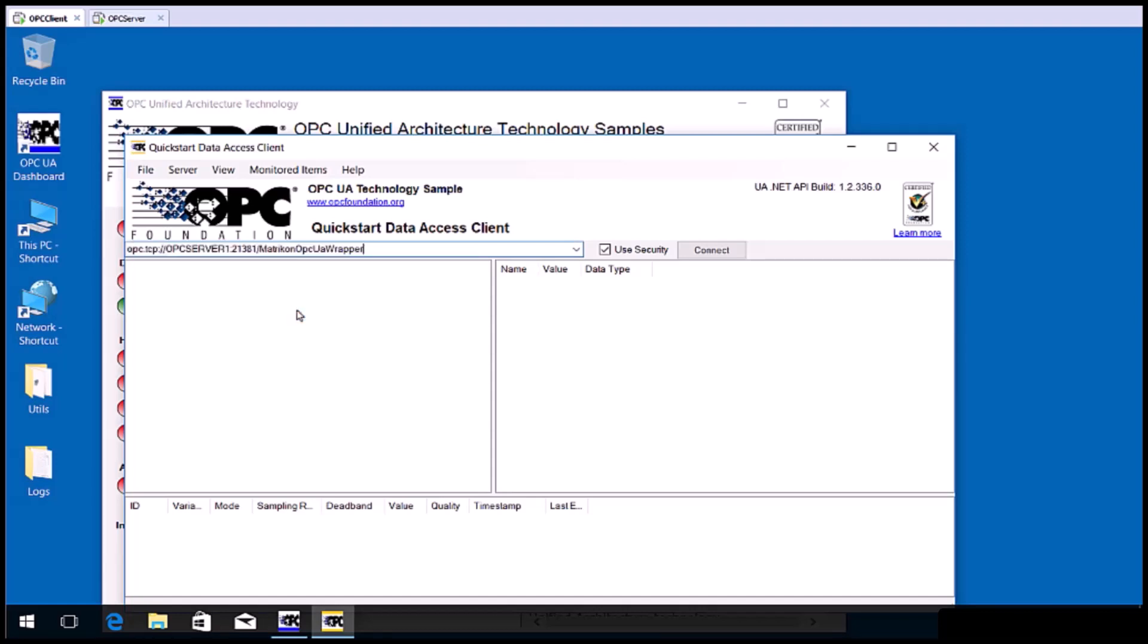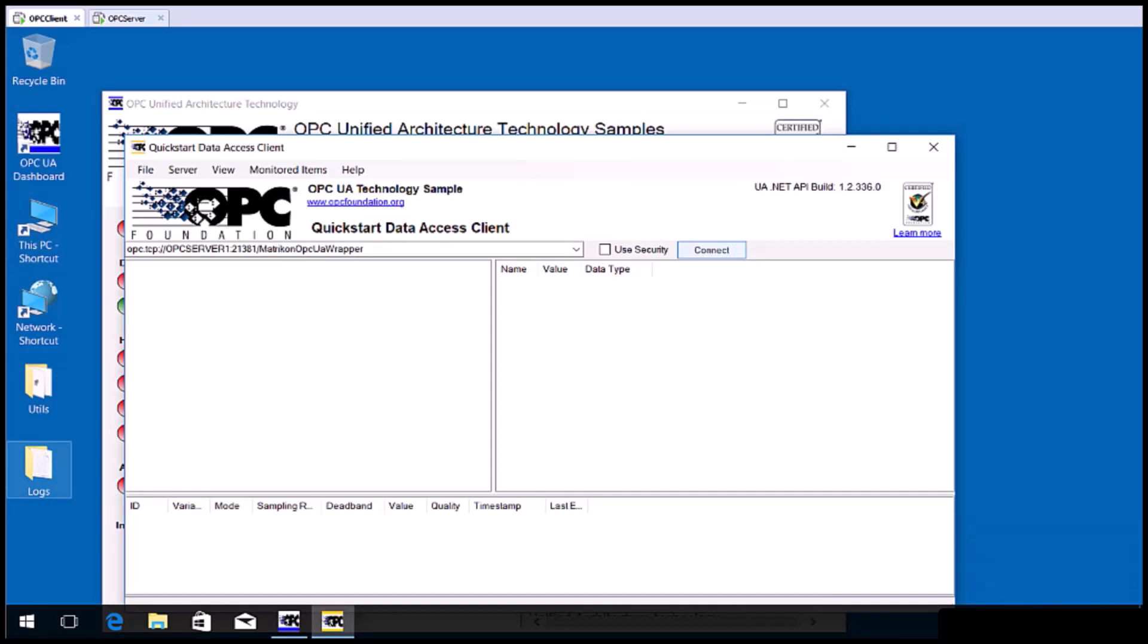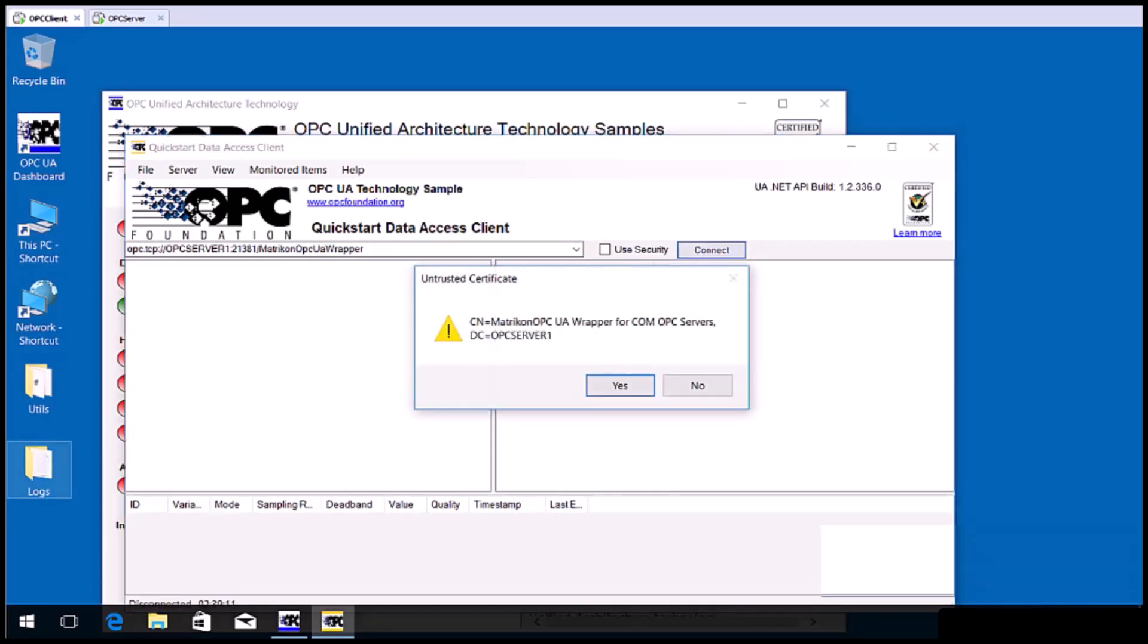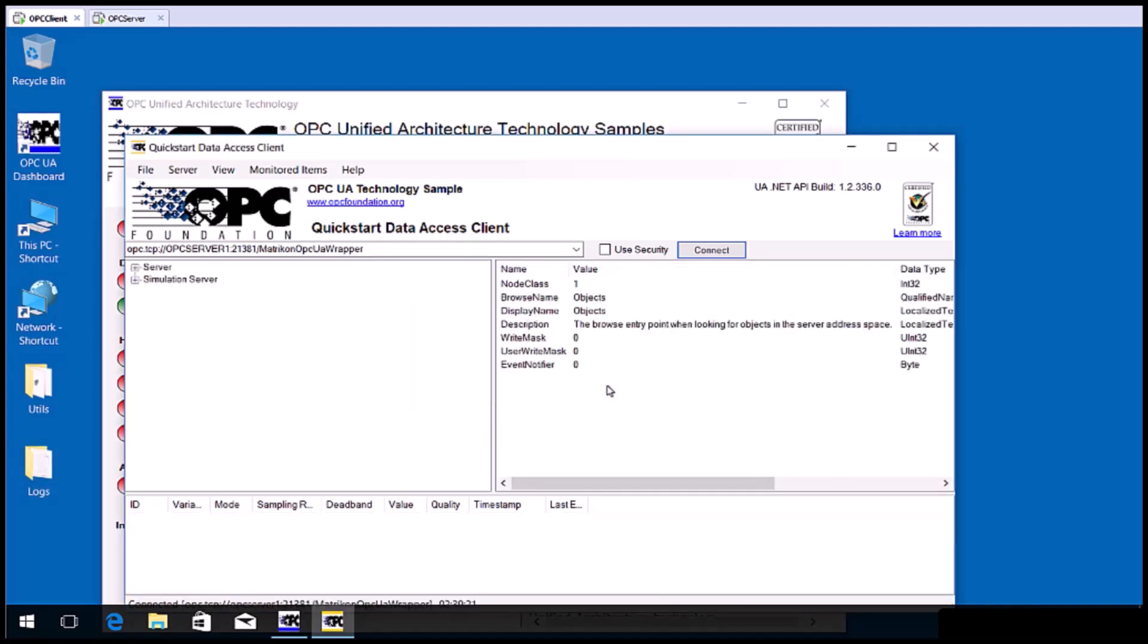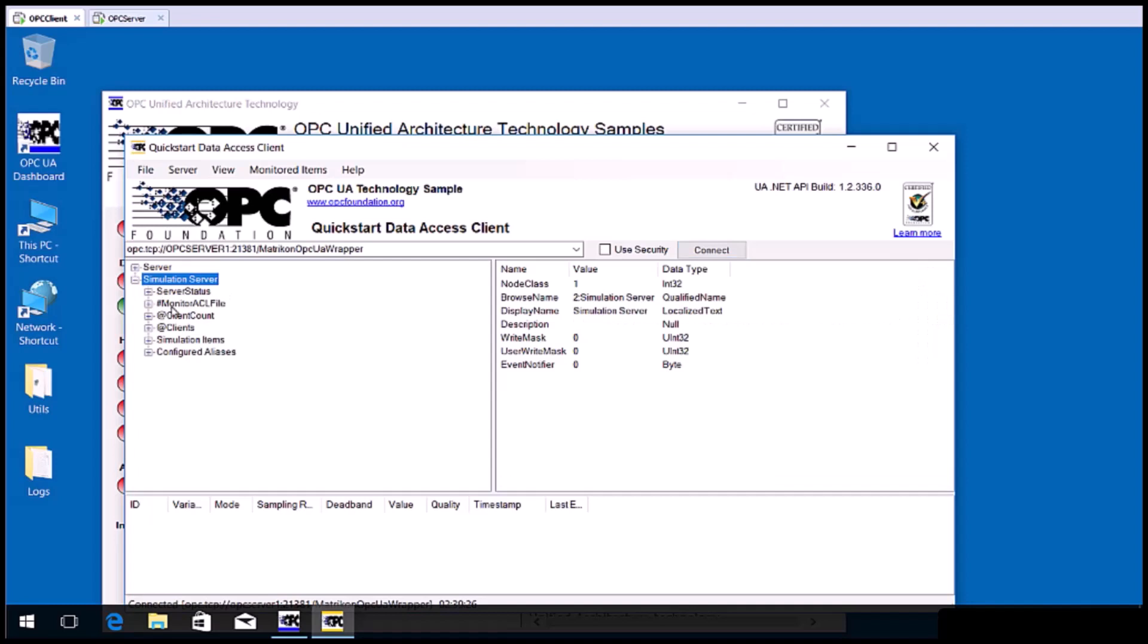Paste the copied URI into here. If you have configured security in Tunneler, enable use security. For this exercise, we will use no security. Now click the connect button. You will receive an untrusted certificate message. Click yes. You can now browse the classic OPC server with this OPC UA client and add tags.